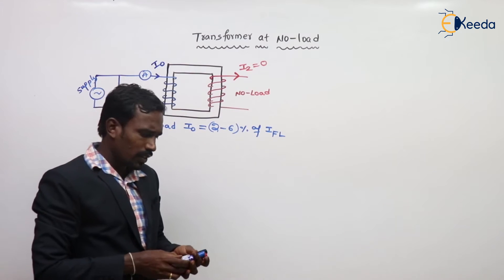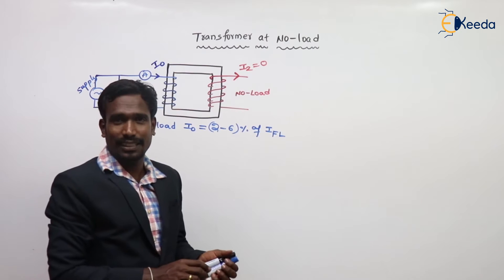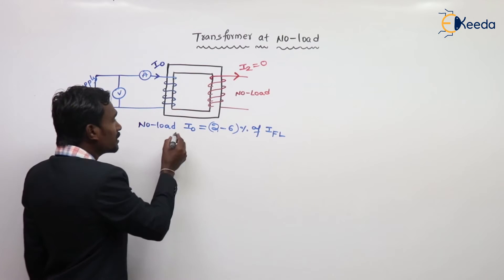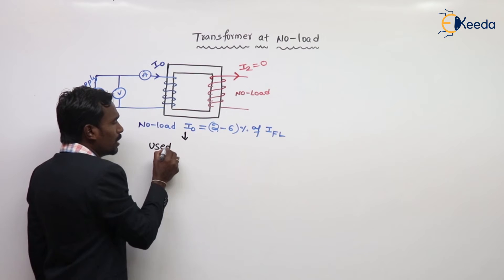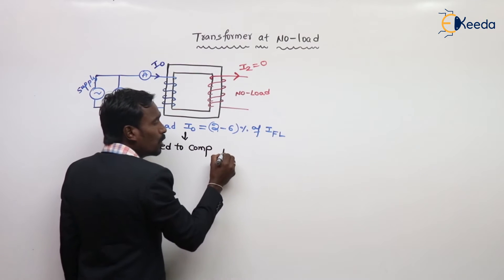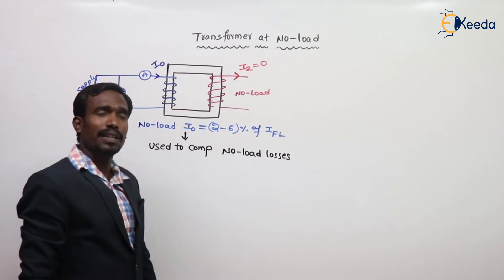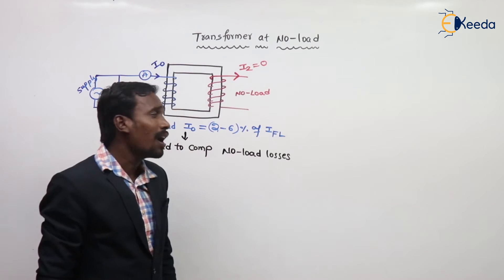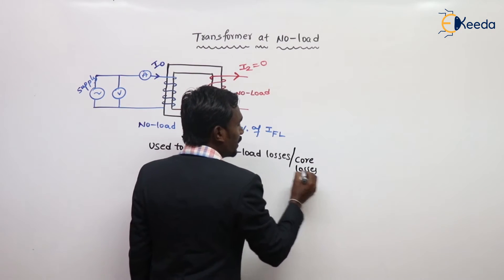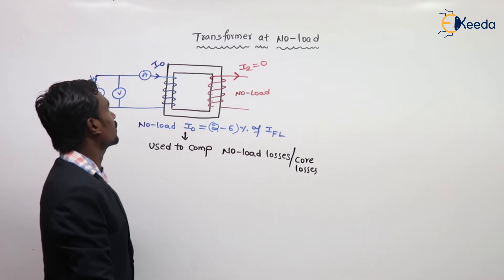This is important. Why does this no load current exist? In general, the transformer should not draw current, but here the transformer draws a small current. This no load current is used to compensate the no load losses, or core losses, of the transformer. This is my no load current I0, with a value around 2 to 6% of full load current.